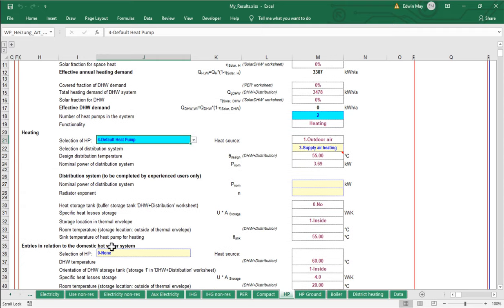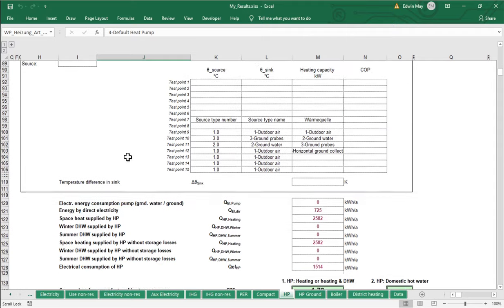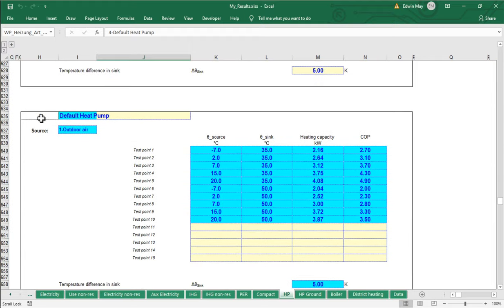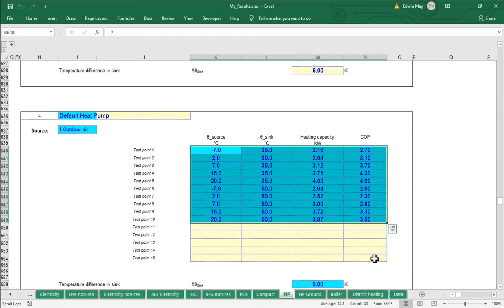We are not using a heat pump for our hot water system, just for the heating system. Scrolling down further, we find entry number four — the default heat pump — with a whole table of performance information. This table essentially describes the performance curve of the heat pump equipment, because heat pumps operate at different efficiencies at different temperature levels. Different outdoor conditions affect performance at any given point in time.